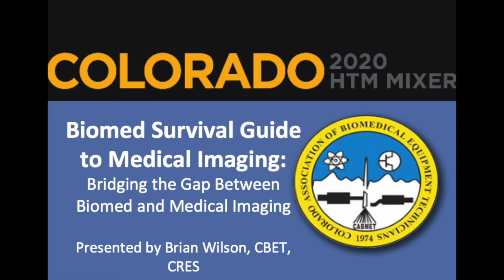After walking around them, I found out these gradients not only have voltage on them, they're also very heavy, because I've had to help change them. It's kind of like you need two men and a young boy to pull one of those gradients out of that cabinet. So you have both voltage and weight, not something a typical biomed would be dealing with, but just be aware that there is high voltage in the equipment room that you may not have taken into account.